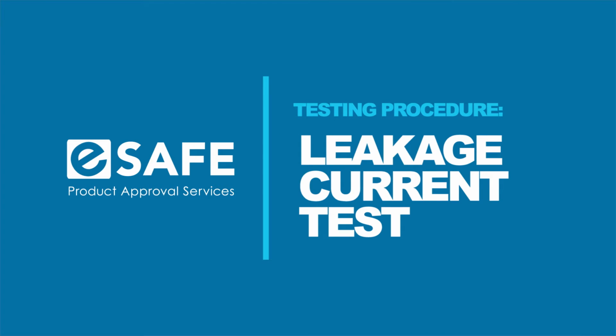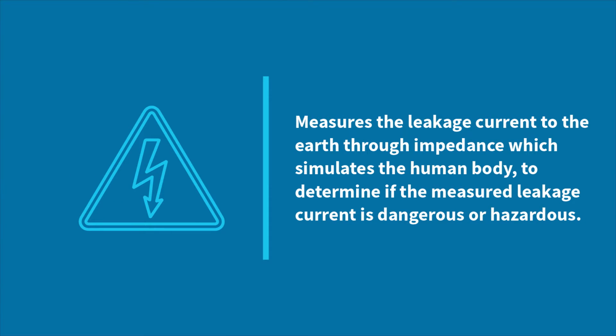Testing procedure. Leakage current test. This test measures the leakage current to the earth through impedance, which simulates the human body to determine if the measured leakage current is dangerous or hazardous.